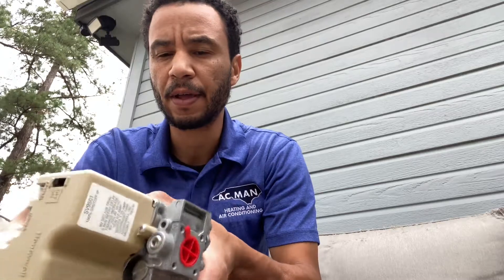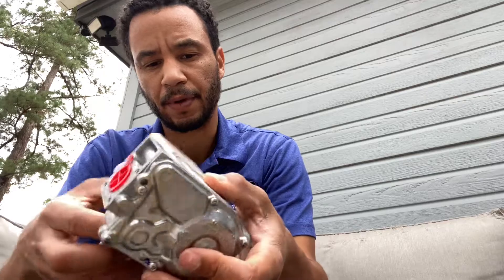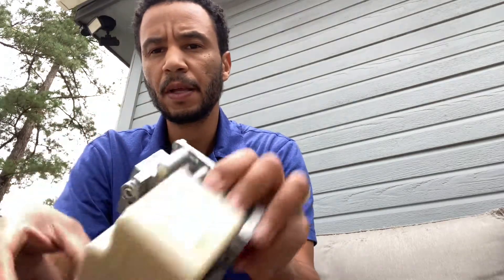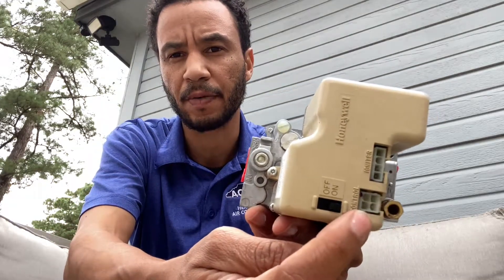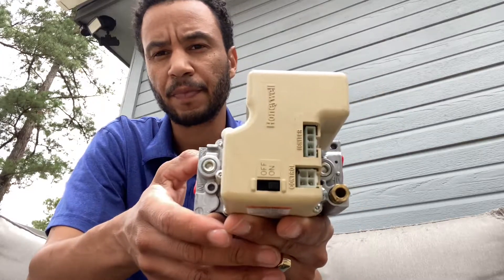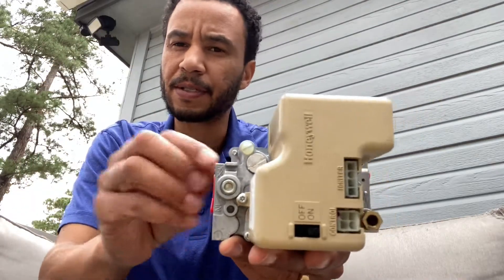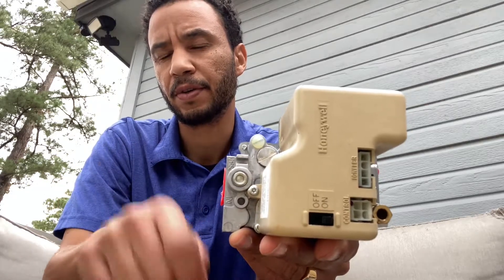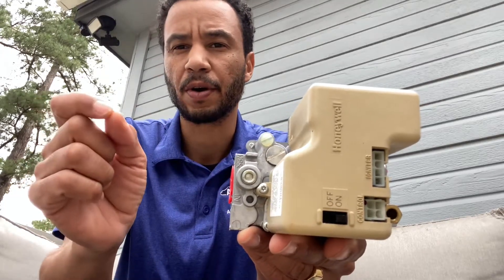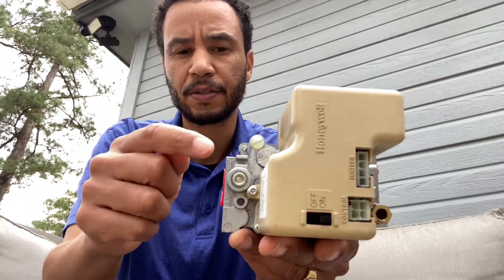Hey everyone, today's video I'm going to show you how to test gas pressure and how to troubleshoot a gas valve. This is your typical Honeywell gas valve — this is a smart valve because it has these little things here. If you look on your furnace on the tag, there's going to be something that says manifold pressure. That's going to tell you how much outlet pressure you need to adjust your regulator to.